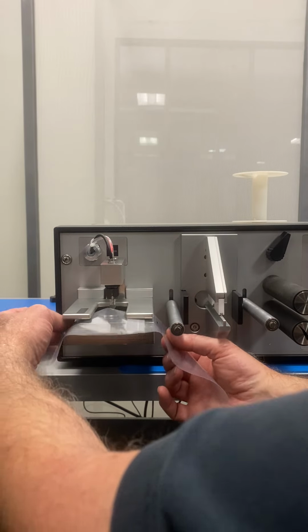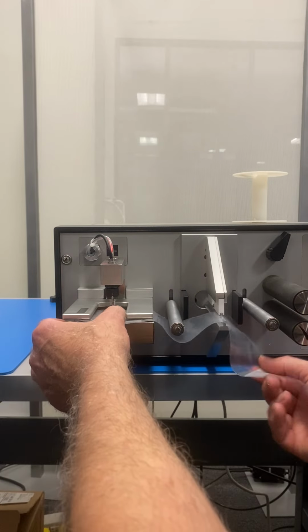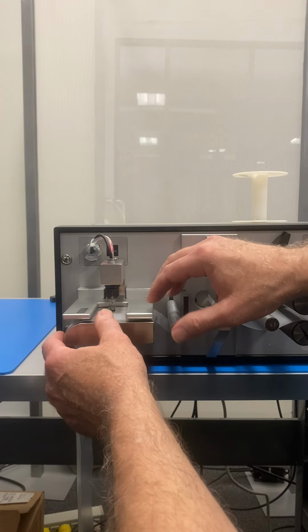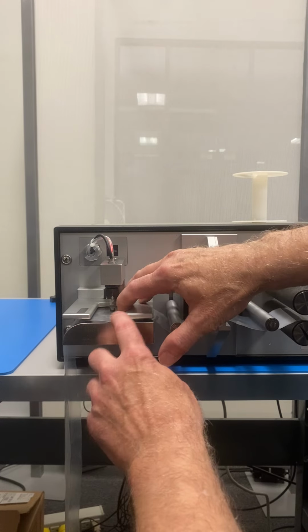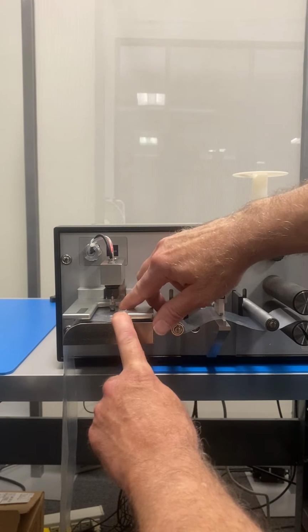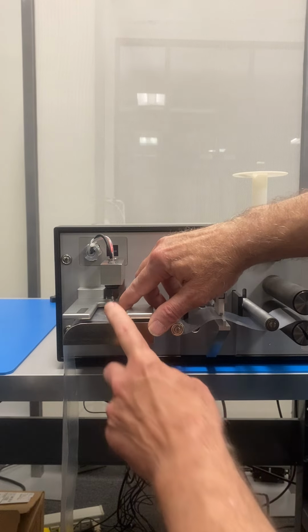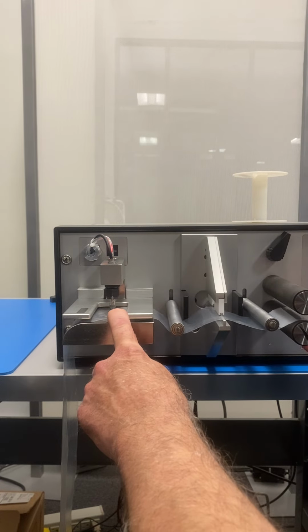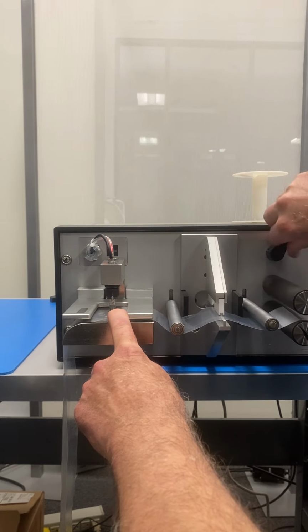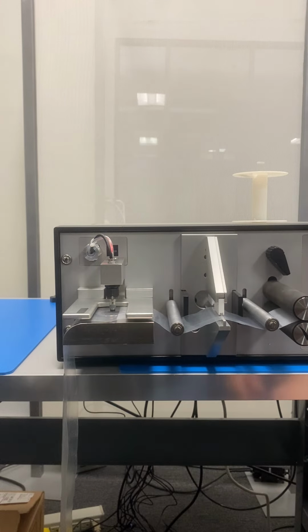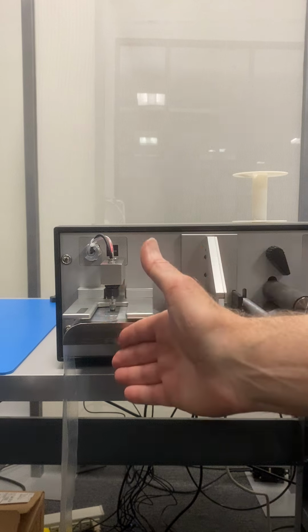So in this example, we would load our sample so that the starting point of what we actually want to measure is just downstream of the contact probe. Feed it through the system as per normal, lower the drive, and then start the test. Again, the contact sensor will take its first point, takes about 1 second.